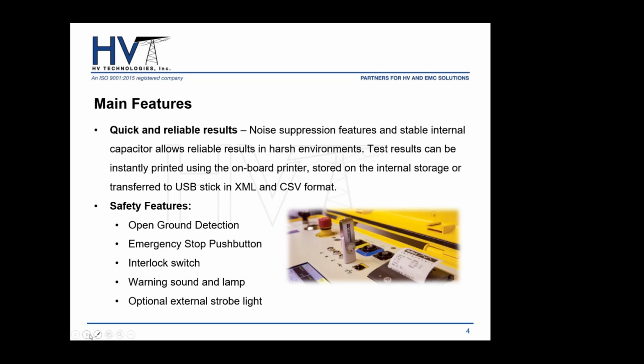We also have, standard with the instrument, our interlock switch, also known as a dead man switch. So before starting the high voltage generation, the user must press the interlock switch button or the foot pedal in order to start the measurement. Once the measurement is underway, you will get a warning sound and a lamp on your touchscreen display. There's also an optional external strobe light that we can offer, which connects to the front panel of the instrument and will also turn on to give that additional visual indication that high voltage is being generated, or that the test object is being tested.